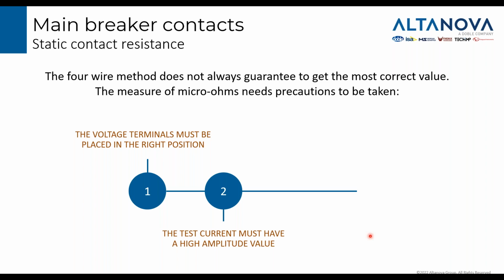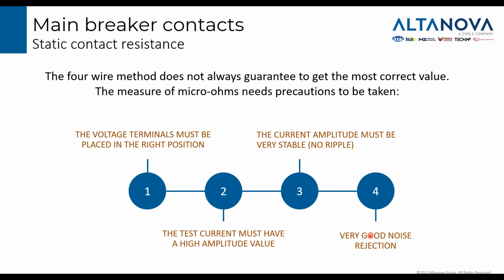The test current must have a high amplitude, because if you want to measure microohms, then you have to inject a very high current in order to be able to measure millivolts at least. If you generate a very small amount of current and then you have to measure voltages in the range of microvolts, for sure it will not be accurate. The current generator that you choose must be very stable, with current without ripples. And when you are in a substation, you have noise, and then you need a device or a method that guarantees very good noise rejection.